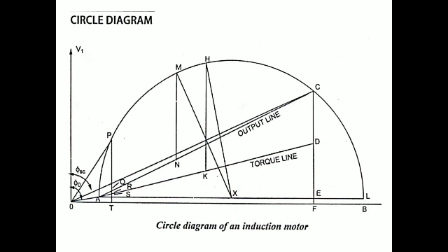Once you complete it, you get this kind of complete circle diagram. So all the notations are there. While making the video, I was not able to make those notations. Now see this diagram to mark all the notations here. That CD is nothing but rotor copper loss, DE is nothing but stator copper loss, EF is nothing but fixed losses. Then a line PT, P, Q, R, S, T is there. That PT is considerably the full load parameters. Then all other things, that M and H, are nothing but for finding the maximum values.